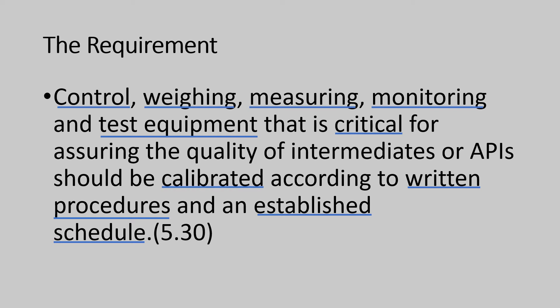It is necessary to calibrate such non-critical equipment also, but the frequency of calibration could be a relaxed one. This is only to establish that the non-critical equipment is in a state of good condition. This would help in optimizing valuable resources, but the risk assessment should be comprehensive enough to establish a clear classification of critical and non-critical equipment.